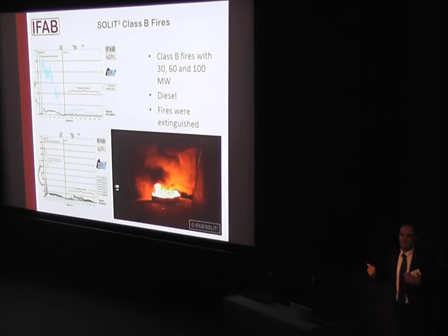So the important area starts around here. There we have the system activated. We still have 60 megawatts, because in this case we are not using this fire switch off, but you have a suppression system, and this system takes time to fight the fire. Then you see that the heat release rate goes down with the pool fire, and then it was off. What you see here in the heat release rates is the so-called reignition of the pool. So pool by pool, we then went through with gasoline and reignited.